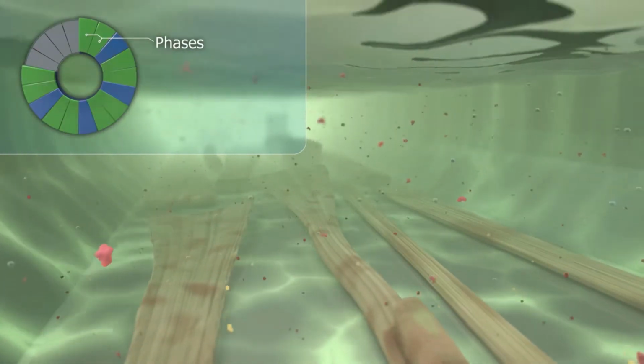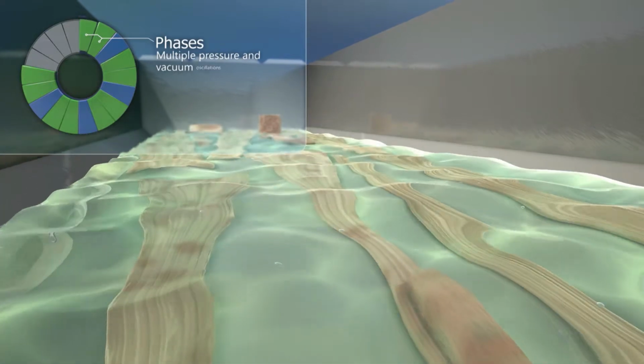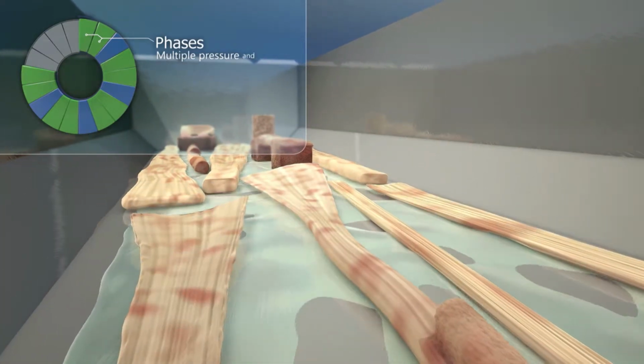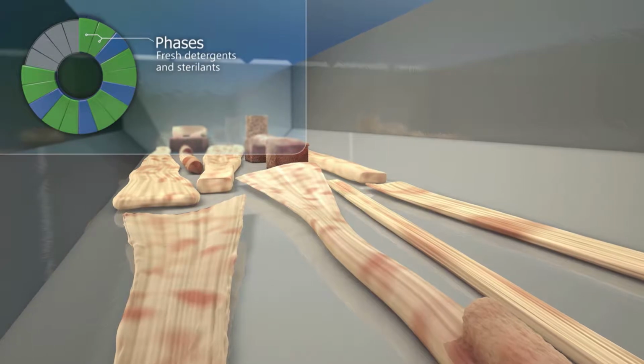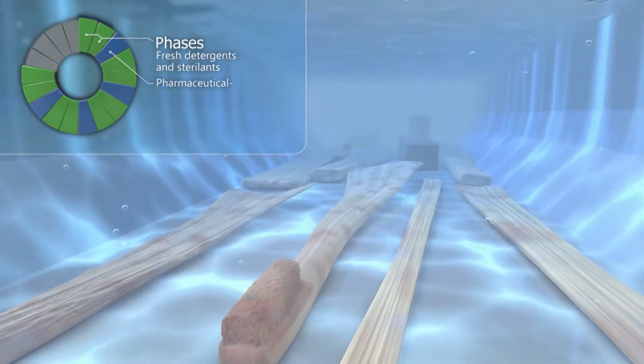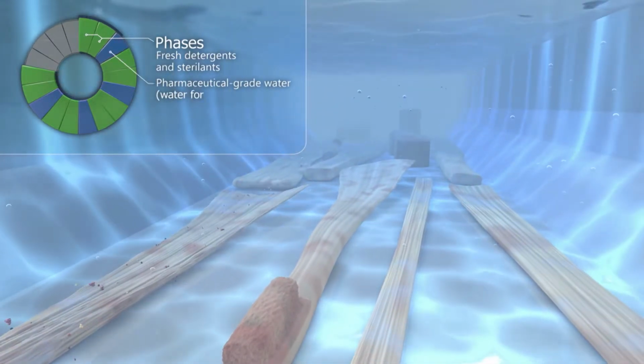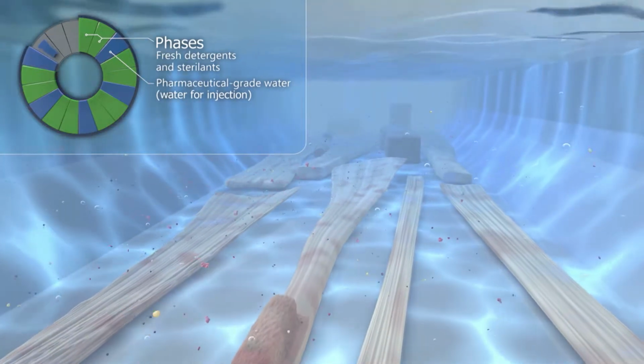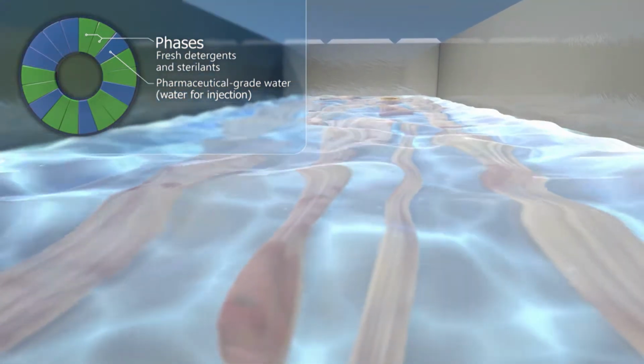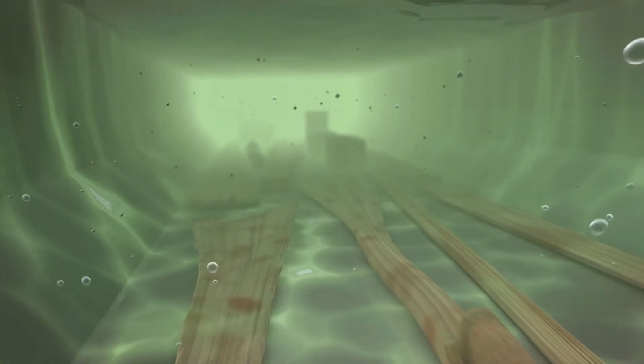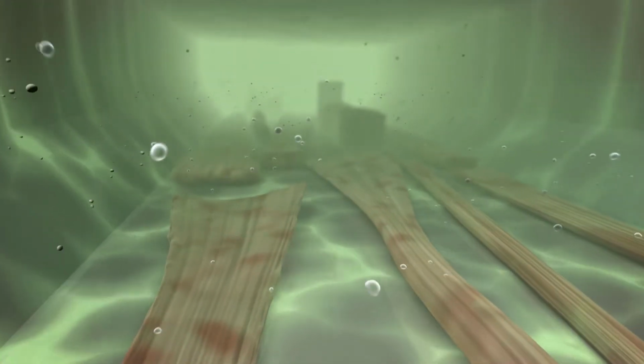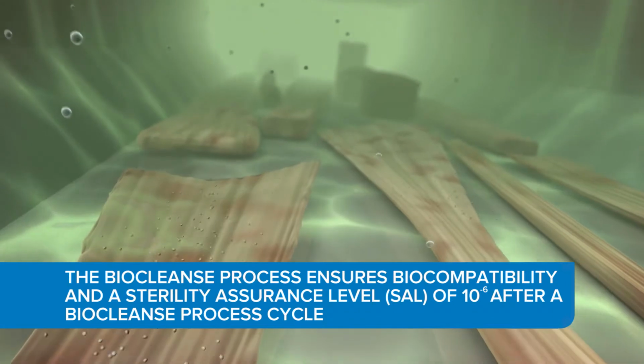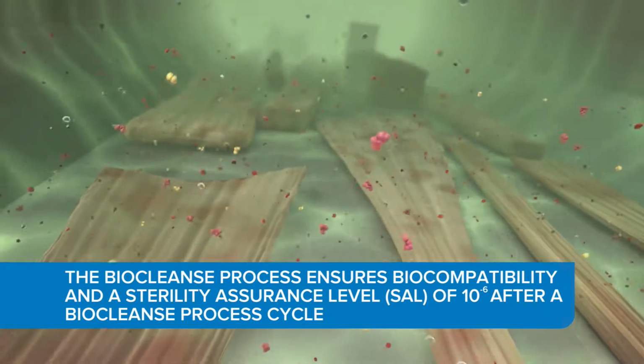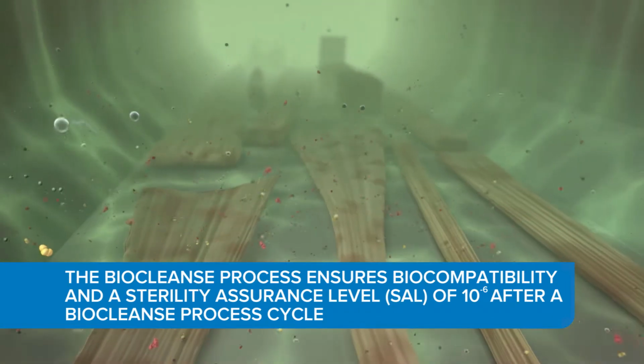Over the course of several hours, tissue is subjected to multiple phases, each consisting of numerous pressure and vacuum oscillations. While some phases are performed with fresh detergents and sterilants, other intervening phases are conducted with pharmaceutical-grade water, known as water for injection, to remove debris. The final phases of pressure and vacuum oscillation are performed with pharmaceutical-grade water to remove residual detergents and sterilants, ensuring biocompatibility and a sterility assurance level of 10 to the -6 after a BioCleanse cycle.